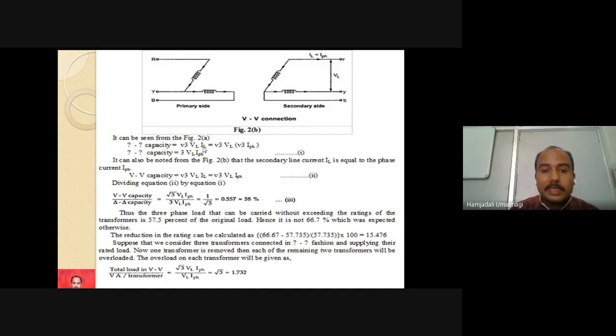For that sake, substitute the value of IL as root 3 times IPH. Now, after simplification, root 3 and root 3 give 3 into VL IPH. So the delta-delta capacity is 3 VL IPH. So the capacity of the delta-delta transformer is 3 times the line voltage multiplied by the phase current IPH.